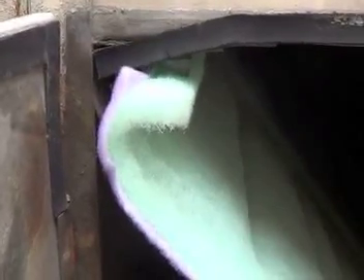So you see he's pushing in the filters from the strong parts of the grid, the top portions, the corners, because if you push the middle it'll bend the grid. Here he's pushing it in, he feels it hit, pulls it out, and you got a complete seal all the way down. You've got gasketing there. The media acts as a gasket. It's a complete seal around the filters, unlike pleated filters. See, there's no play there. Complete seal all the way down, protecting these coils. This is the only way you can maintain peak performance and efficiency throughout your system's operation.